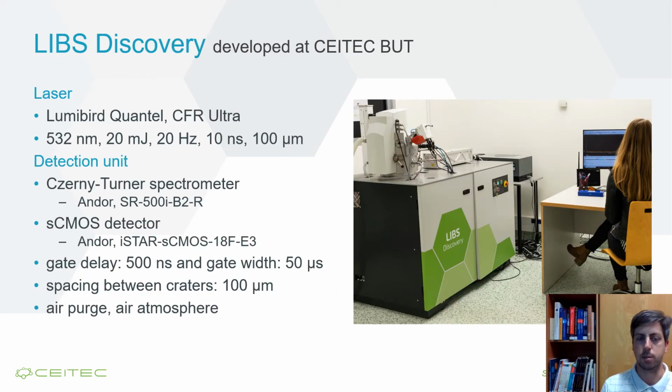For the analysis, we have used LIBS Discovery, which was developed at CEITEC BUT University of Technology. It's a quite fine piece of instrument, and it's using a Quantel CFR Ultra laser source, and the detection unit consists of a Czerny-Turner spectrometer and a CMOS detector, both from Andor. You can see the optimized parameters, and I will speak about them later on.